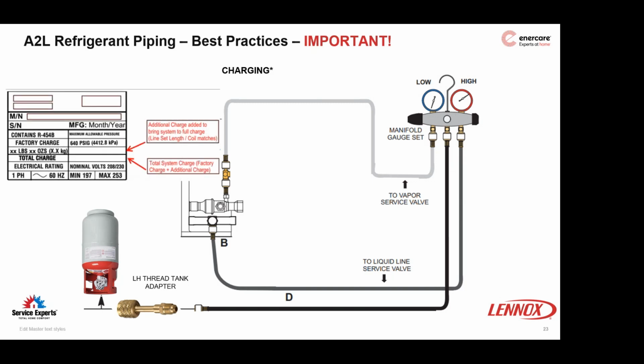Now, Lennox wants you to make sure you mark and tag. I mean, we're going to tag via ODP guidelines, but they also want you to permanently mark their tag outside for any additional charge you're putting in, so that you have a total charge listed on the outdoor unit, right on the nameplate. So if you could write in something permanent, like an ink, or if you're Anthony, then you might even have a label maker. You can put a label right on it. You can make a nice digital label and print it off.